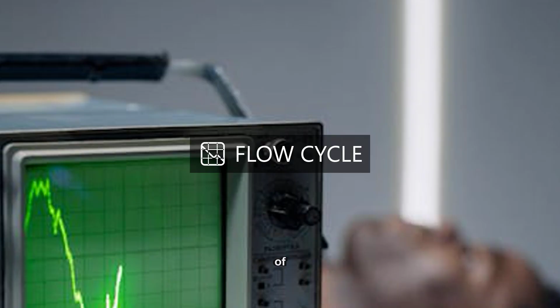Each breath is flow cycled, stopping when inspiratory flow drops to about 25% of peak. This prevents overinflation. Pressure support is not suitable for apneic or deeply sedated patients. It requires intact respiratory drive.